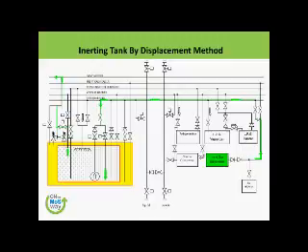We have simply started our IG plant or IG generator, pushed the IG in the liquid header, and then we are throwing it in very slowly. We are pushing it down into the tank, and automatically the light air is going out through the ventilation header.